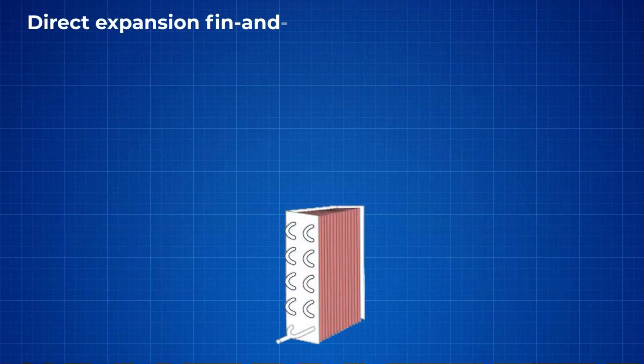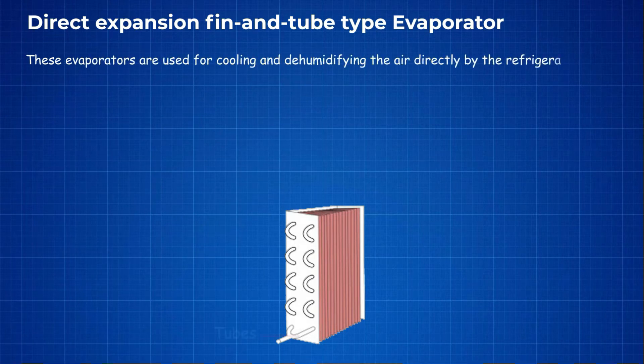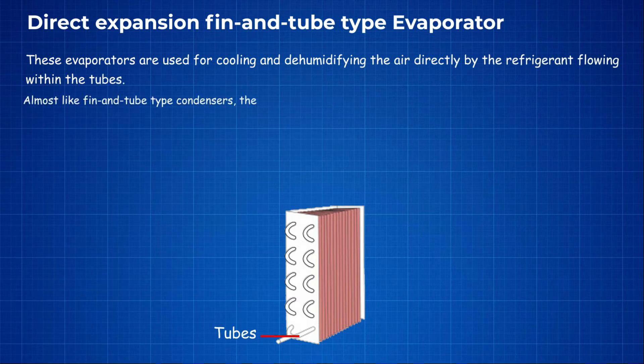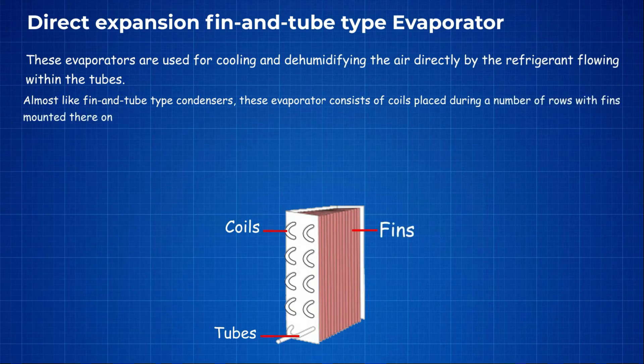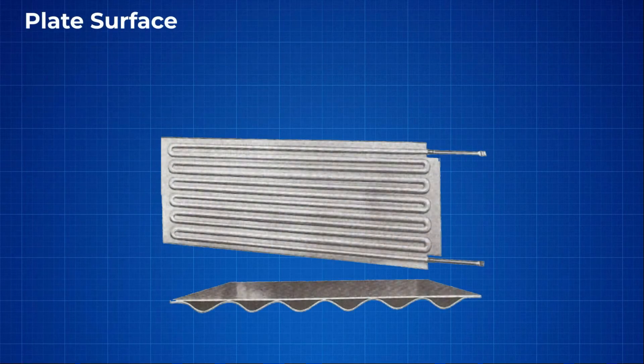Direct expansion fin and tube type evaporators are used for cooling and dehumidifying air directly by the refrigerant flowing within the tubes. Similar to fin and tube type condensers, these evaporators consist of coils placed in a number of rows with fins mounted on them to extend the heat transfer area. Tubes with individual spiral straight fins or crimped fins are welded and are utilized in some applications like ammonia.